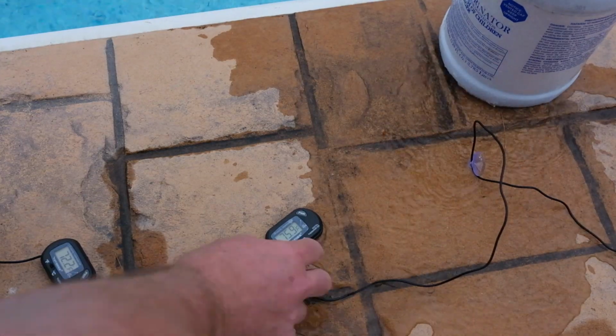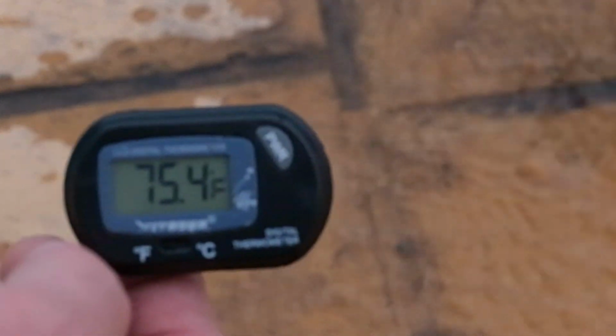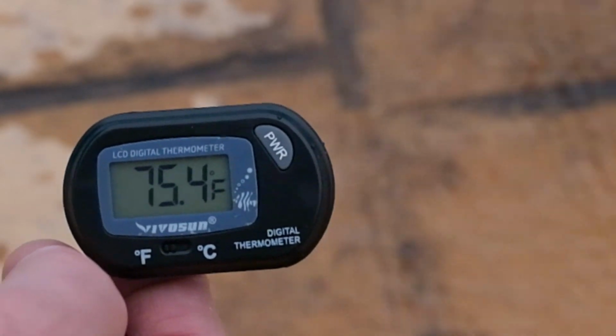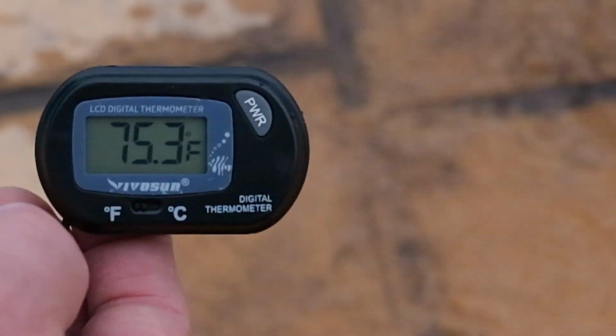All right, so you want temperatures, you got temperatures. We have two readings: one from the pool itself, which is about 72.2 degrees, and one from the jug coming from the house, which is 75.4. So about a 3-degree rise coming from the heat exchanger, which isn't terribly bad.